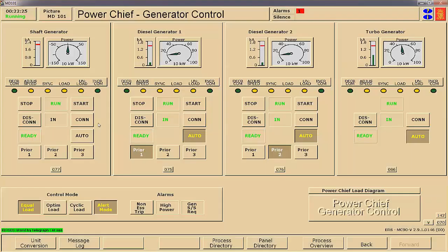So at departure now we can start switching over our generators. We're going to go to the generator control, take it out of alert mode, take all generators out of auto, and the first thing we're going to do is shift power from the turbo generator to diesel generator number 2. So I'm going to bring up the turbo generator on this page.